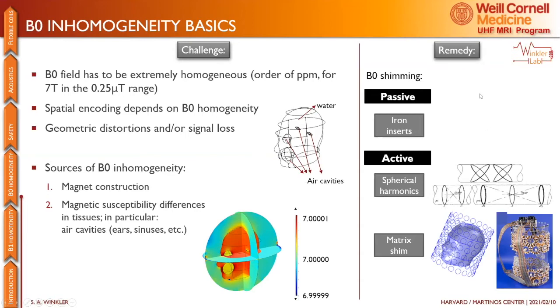remedy this situation, there is a passive approach that corrects for magnet construction. So when a magnet is sited, they have little rails. They put these little iron inserts into the rails. It seems a bit like black magic, but they figure it out mostly, which I'm always impressed by. But when it comes to the in vivo situation with the patient-dependent susceptibility differences, you use actual coils that correct for these. Traditionally, vendors have used spherical harmonic coils. Because this volume of interest is spherical, it's easy to decompose that into spherical harmonics. And it's easy to build coils that act on one specific harmonic. So this is, I think, the second order and so on. I don't know exactly, but yeah.